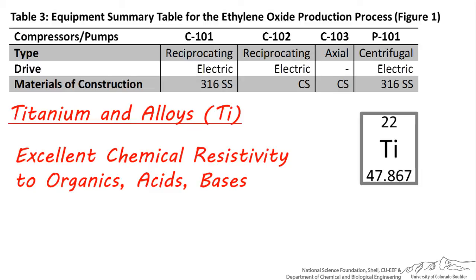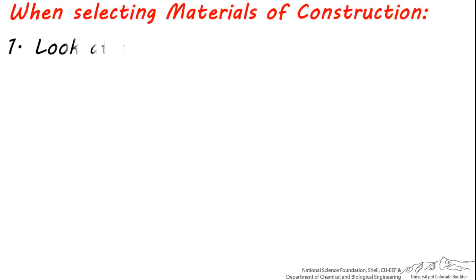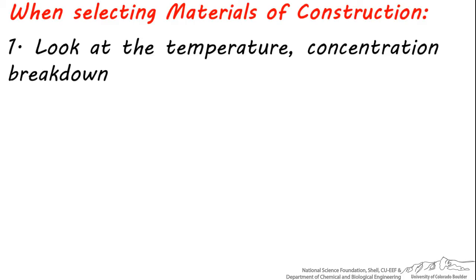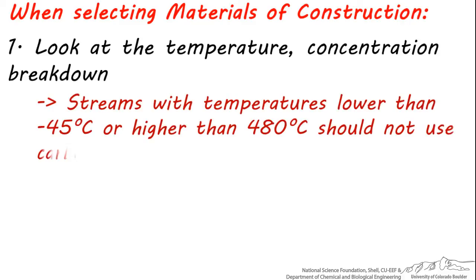Next, we'll discuss how you should incorporate all this information to make an appropriate selection for the type of material for each piece of equipment. When selecting a material, look at the inlet and outlet temperatures and the concentration breakdown of all components in the stream or streams going through the equipment. Check to see if the temperature is below minus 45 or above 480 degrees centigrade — if so, you should probably not use carbon steel, and will need to consider stainless, nickel alloys, or other options.